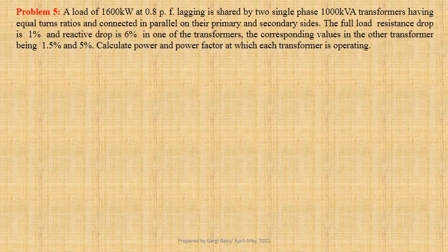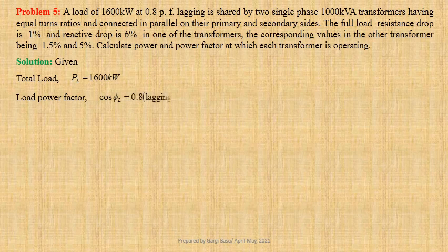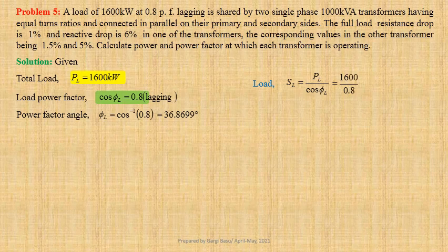Let us first write down the given data. Total load PL equals 1600 kilowatt. Load power factor cos phi L equals 0.8 lagging. Let us now determine the power factor angle. Phi L equals cos inverse 0.8, that is equal to 36.8699 degree. Load in kVA, SL equals PL divided by cos phi L, that is equal to 1600 divided by 0.8, that gives us 2000 kilovolt ampere. Load in phasor form, SL equals 2000 kilovolt ampere at an angle minus 36.8699 degree.